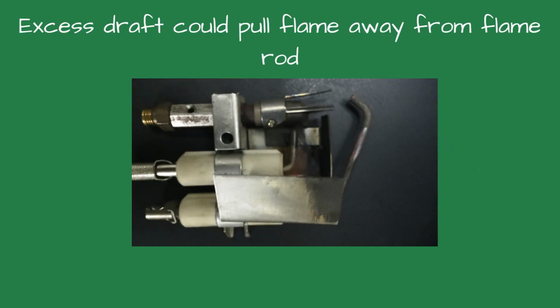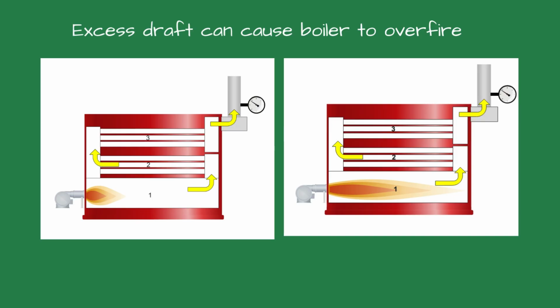Ever wonder why your boiler is getting pilot flame failures? Check your draft. Excess draft can pull the flame off the thermocouple or flame rod, causing intermittent shutdowns or lockouts. Steam boilers are especially susceptible to draft issues.